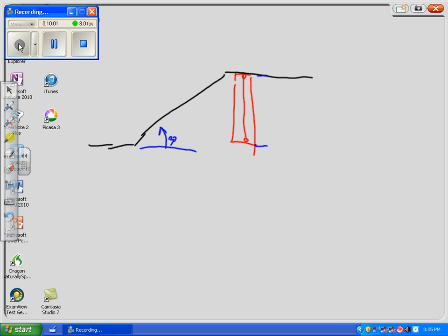We can take this distance here. Let's say this is 9 inches from top to bottom. We can just take that distance and double it and mark where we want the first bend to be on the conduit, and then go down twice that distance and put another mark on the conduit and bend it 30 degrees up at this one, flip it over, bend it 30 degrees back that way, and it'll come out perfect every time. The problem with that is what?